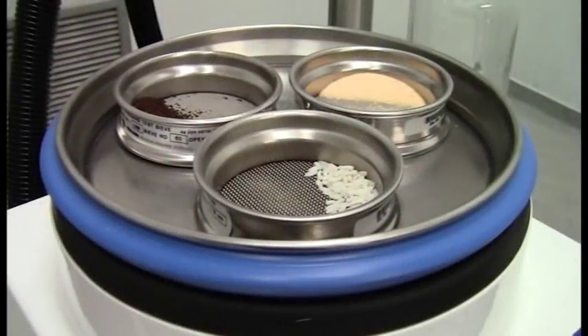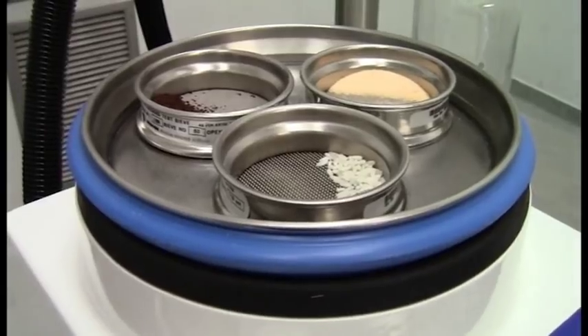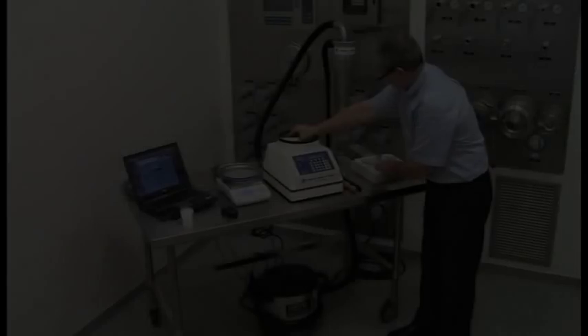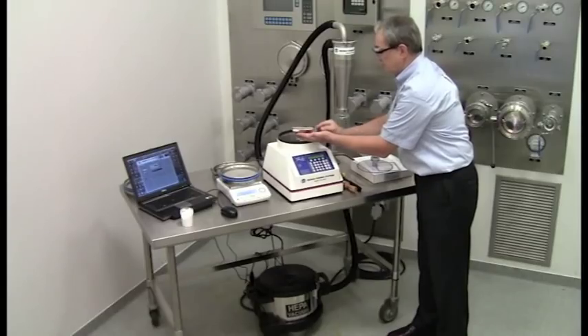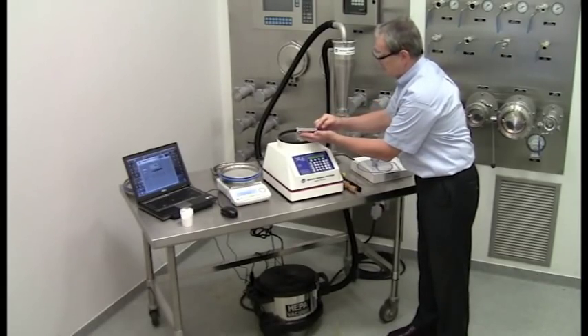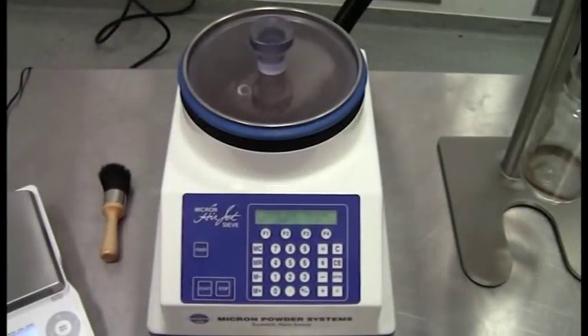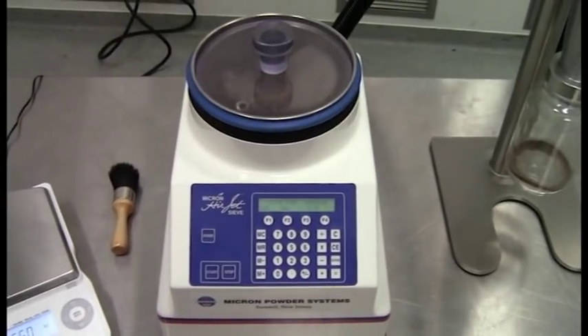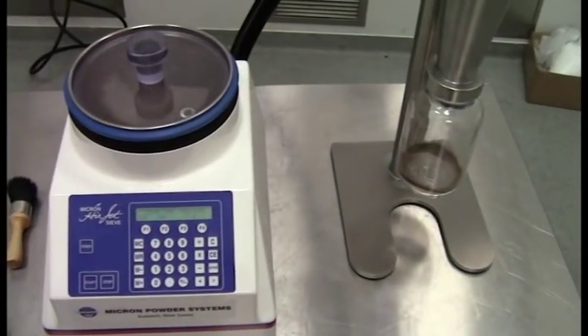Precise particle size can quickly be determined at sizes from 20 to 4750 micron. The unique rotating wand method also eliminates the need for tapping or brushing and increases reproducibility with controlled measurements of pressure drop and duration.